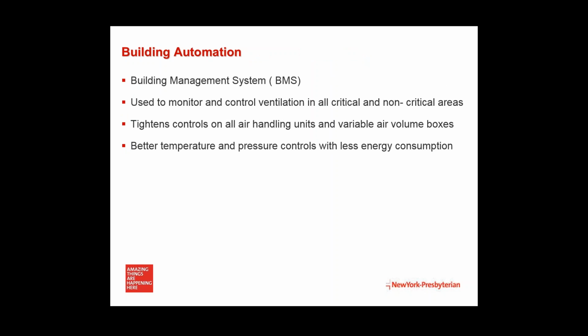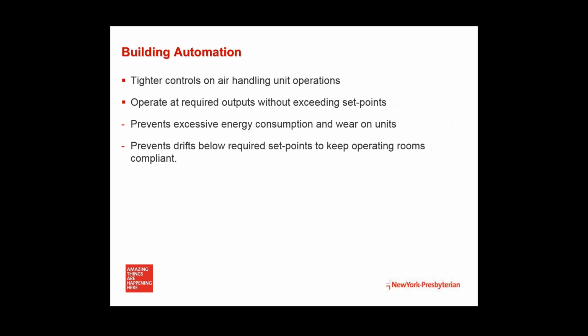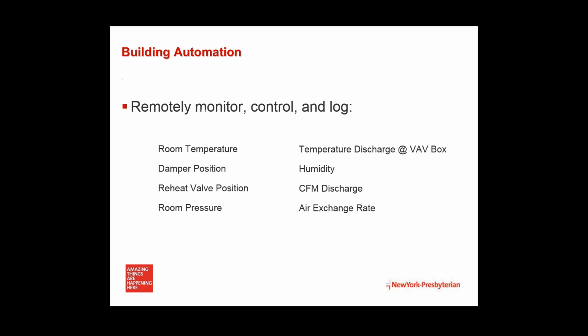So utilizing the building management system, we work at the mandatory outputs without exceeding requirements, which would use excessive energy and wear out components. It also prevents drifts below the required range to keep our operating rooms compliant and safe. We have remote digital monitors on all the critical environmental points in the ORs at the Allen Hospital. Next slide, please. One more slide.